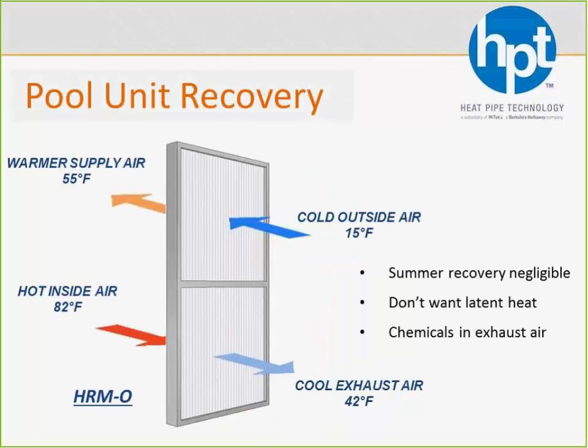So another cool thing we can do is do what we call our over-under heat recovery module, or the HRM-O. In this case, we just take the HRM and flip it up 90 degrees. The obvious downside there is now we're only going to get heat recovery when the warmer airstream is at the bottom, but there are plenty of applications where that's all that matters anyway.